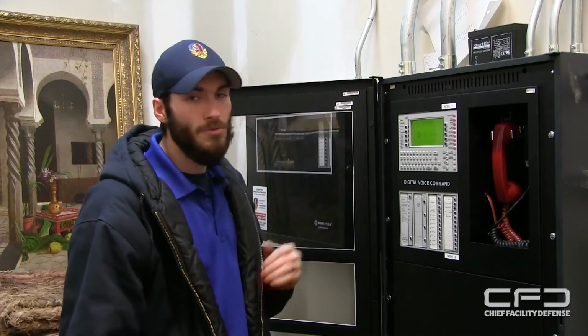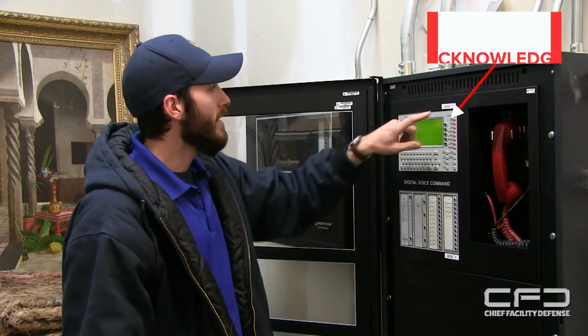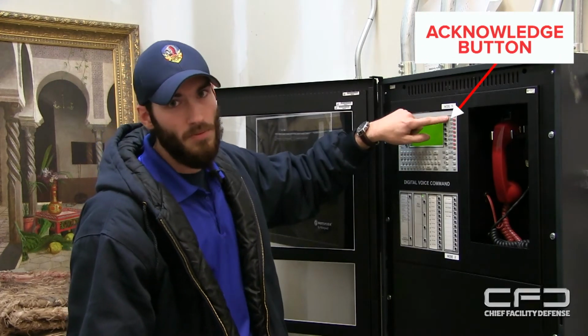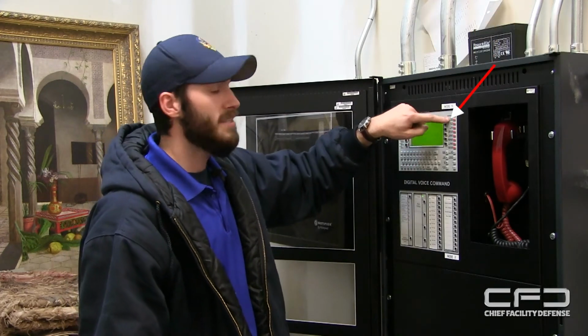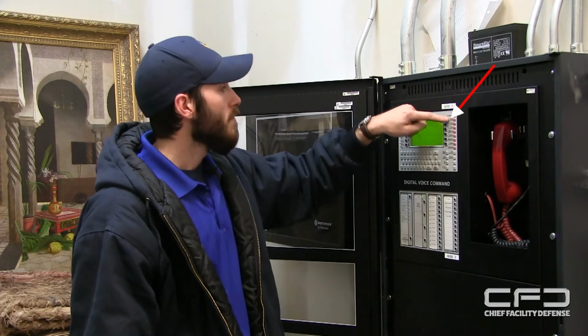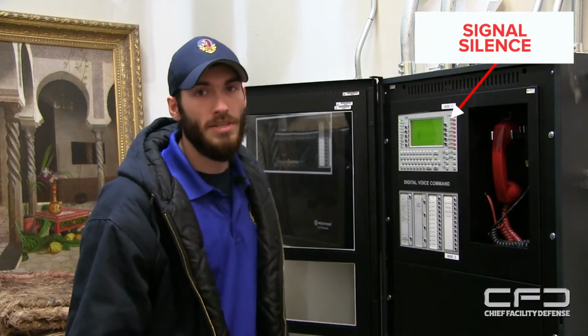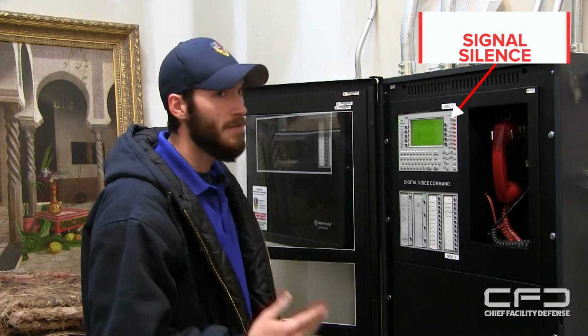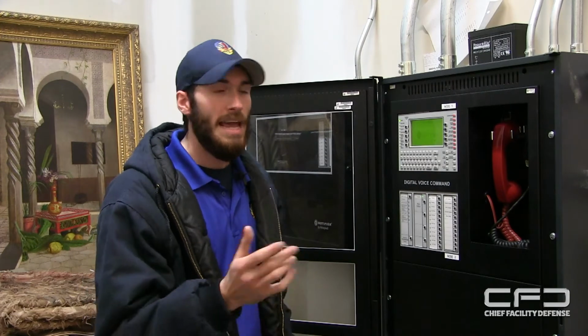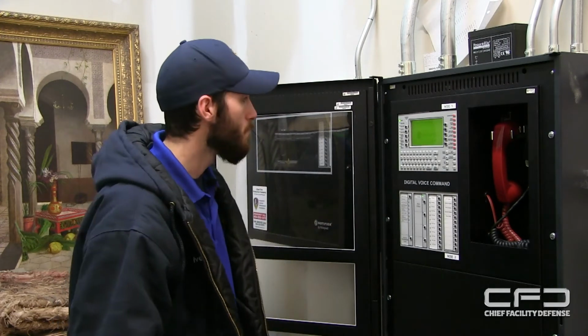If that is the case and you know that it is a false alarm, you can hit the acknowledge button on the top right hand side, and then the signal silence button, and then you can try to do a system reset. Now if for some reason a smoke detector might have gotten some debris in it, maybe got dirty, you will need to locate that smoke detector to clean it or spray it out with air and then try to reset the panel, and that will clear the system of its fire alarm.